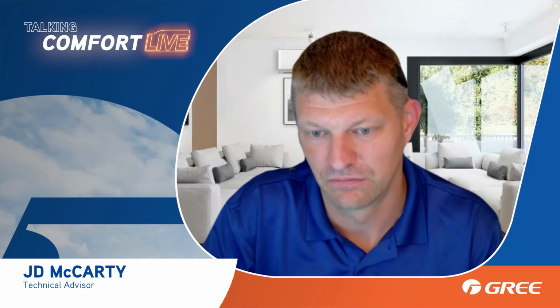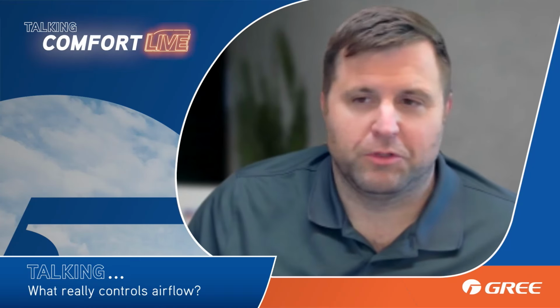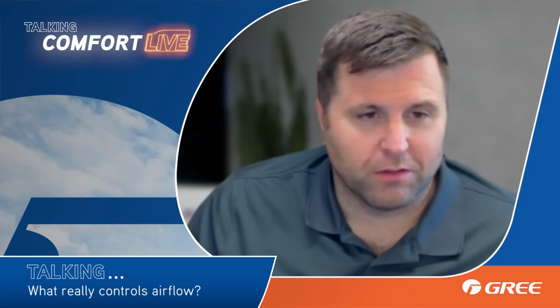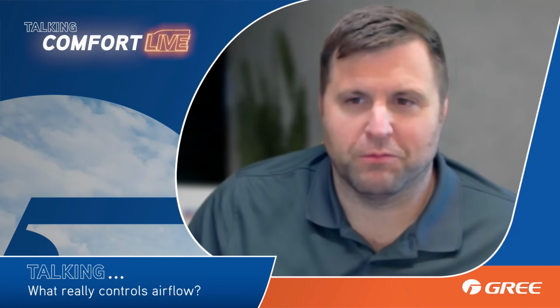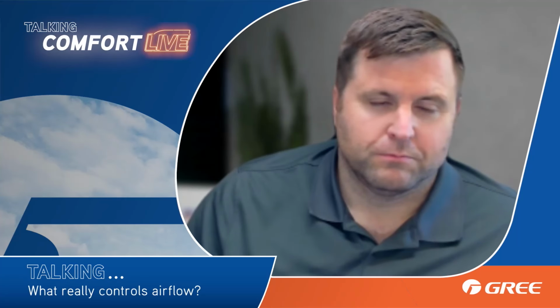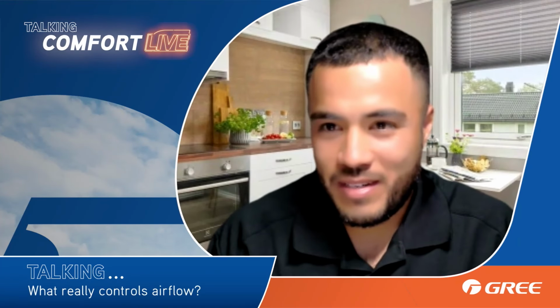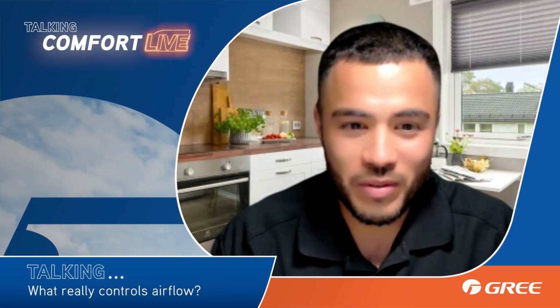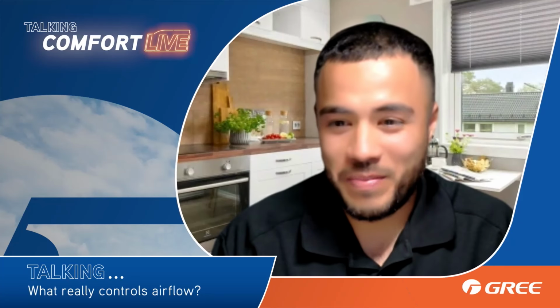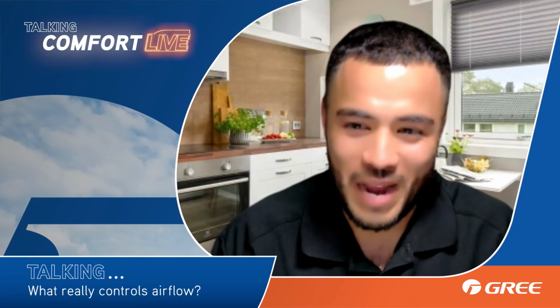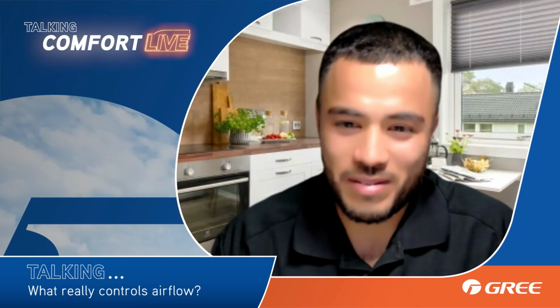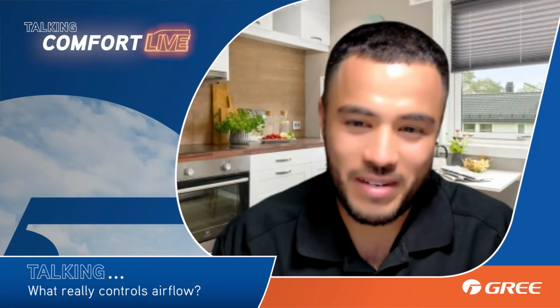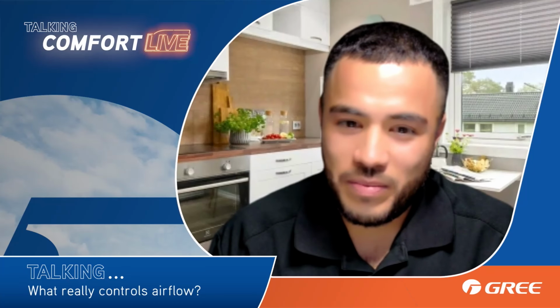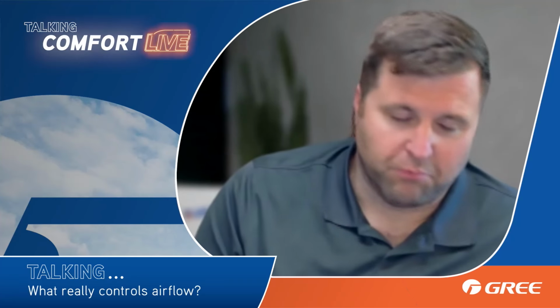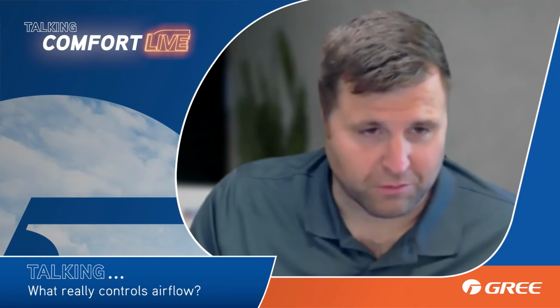Okay. And speaking of low, if the airflow is too low, whether that's from a set point, ductwork, dirty filter, or dirty coil, what kind of problems can we have there? Well, all sorts of problems, Dan. You're talking freezing, you're talking compressor discharge temperatures being too cold, where the refrigerant doesn't boil off in the coil. If you run into that, you're talking a technician coming out to your house or business, because more than likely the system is down for some odd reason. Right. Yeah, absolutely. As far as freezing, most of the time we're not going to get much of an opportunity to freeze because our systems have freeze protection to prevent it.